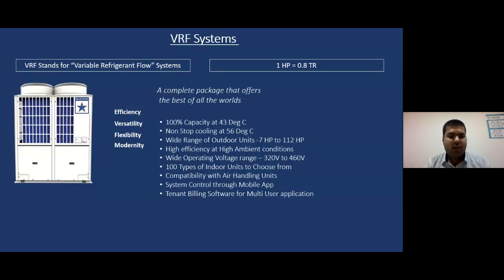that if I install a 2-ton split AC, which has a single indoor and single outdoor unit, at 35 degrees Celsius my machine would give 2 tons, but after that an individual split AC would derate. It would give 1.8, 1.7, 1.5 tons, which means less cooling and increased power consumption. That is why we have most of the time observed that our light bill goes up in summer. What VRF does is it is designed for 43 degrees Celsius. Up to 43 degrees Celsius my 2-ton machine would not derate, and after that the machine would derate, and it would give non-stop cooling at 56 degrees Celsius and would not trip up to 56.